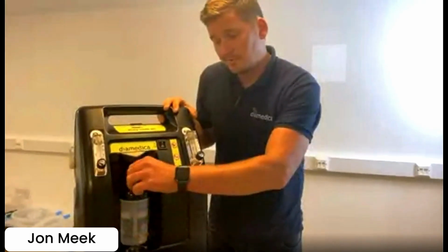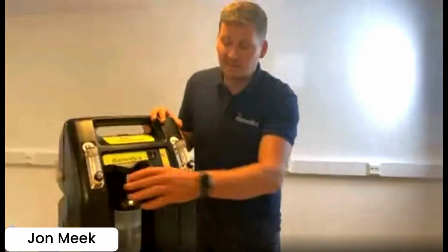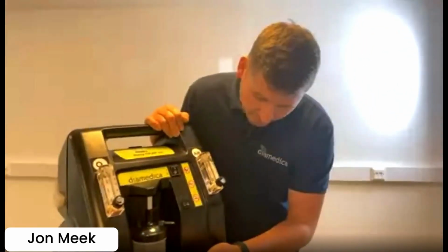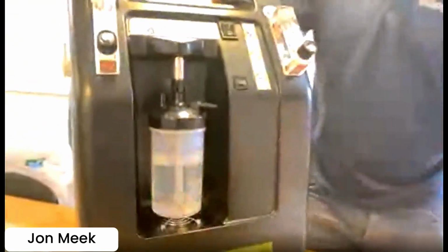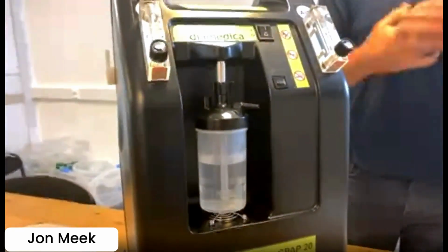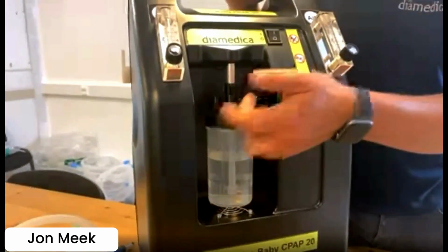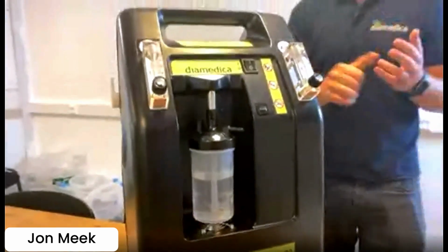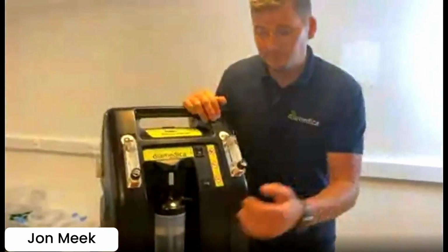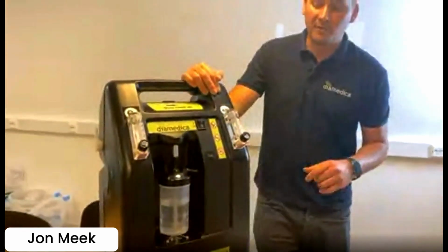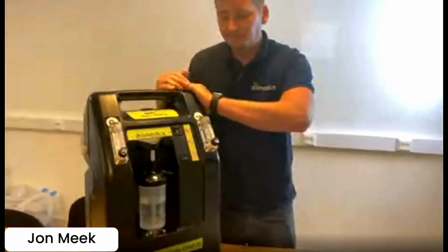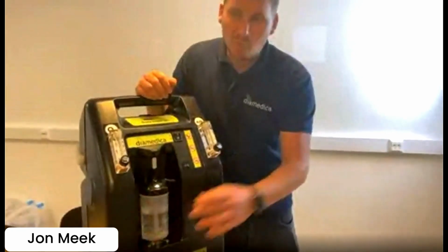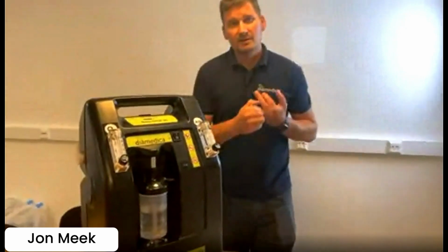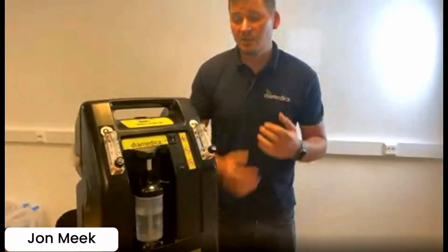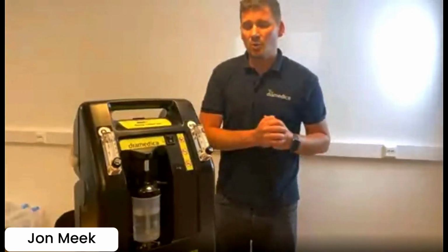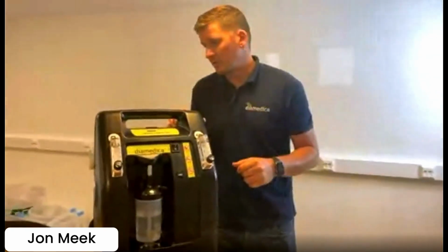On here, the humidifier bottle is fitted. Be careful. The plastic fitting doesn't need to be done up too tight, otherwise it can break. On the front here, the humidifier bottle has a minimum and a maximum. Do not overfill the humidifier bottle on any of the machines, because if you do, moisture will flow out into the circuit, and then you'll affect the pressure and flow going into that circuit if the moisture becomes too much. So ensure that it's not filled above the maximum, depending what humidifier bottle you have fitted. The bottle must only be filled with sterile water or water that's been boiled and allowed to cool. You cannot just use tap water, as you will provide bacteria or anything in that water to the patient and can cause illnesses further to what they've got.